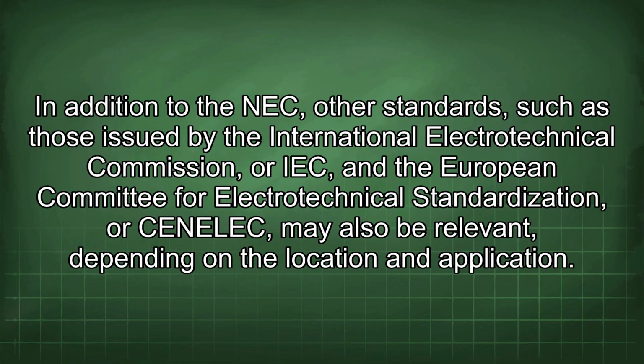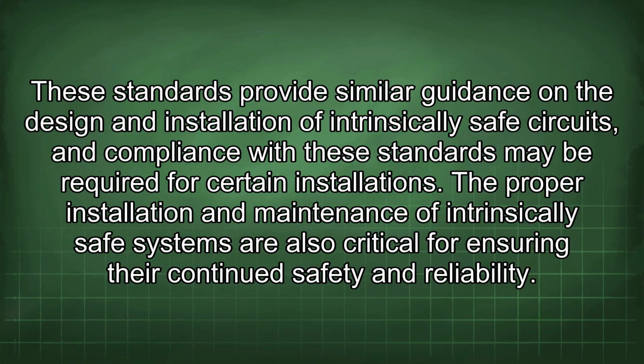In addition to the NEC, other standards, such as those issued by the International Electrotechnical Commission, or IEC, and the European Committee for Electrotechnical Standardization, or CENELEC, may also be relevant depending on the location and application. These standards provide similar guidance on the design and installation of intrinsically safe circuits, and compliance with these standards may be required for certain installations.